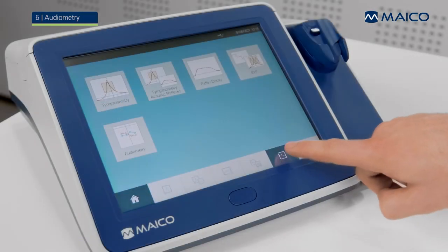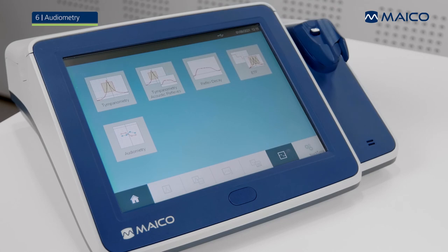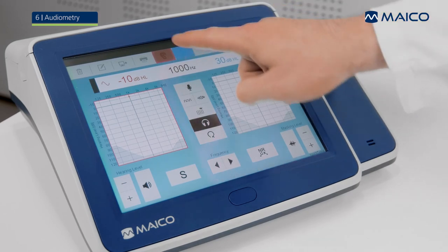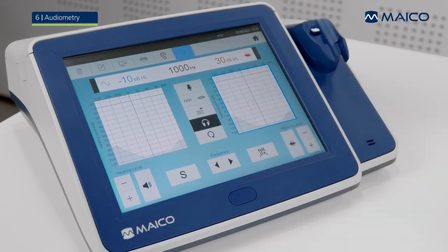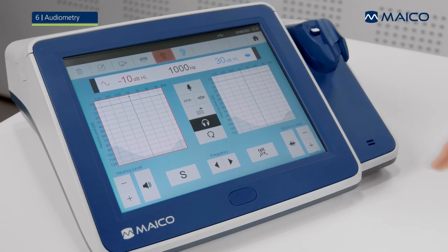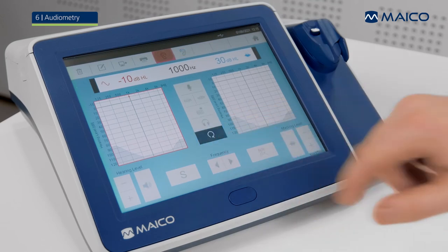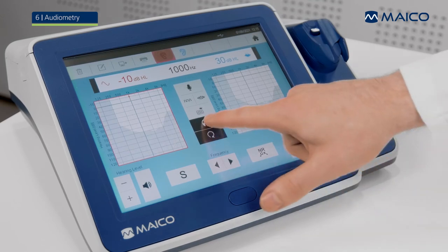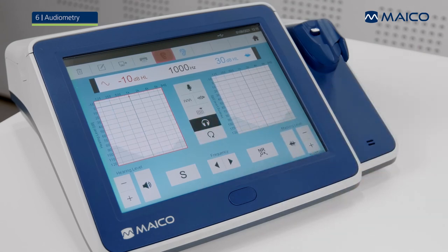Select the audiometry icon from the home screen or fixed function bar to navigate to the audiometry screen. The audiometry screen displays the audiograms for right and left ear and some control buttons. With the ear side selection buttons on the top, you can select which ear is measured. Depending on the device configuration, the transducer button lets you control whether air conduction is recorded or bone conduction is about to be measured.